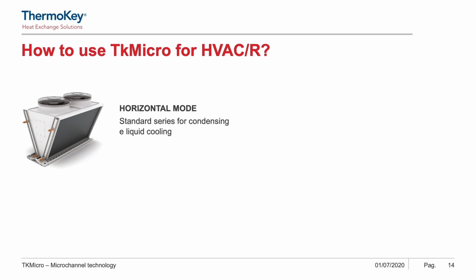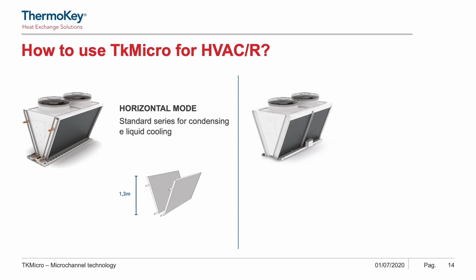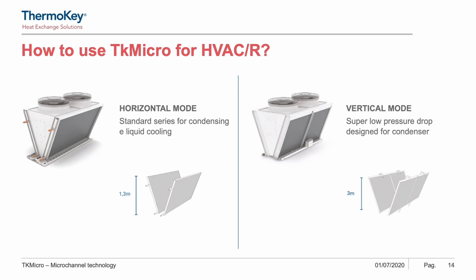Microchannel cores can be integrated within typical V-type modules for chiller applications. Tube could be horizontal or vertical. In the first case, connections are on one or two sides, whereas in the second case, connections are on the top and on the bottom of the module.